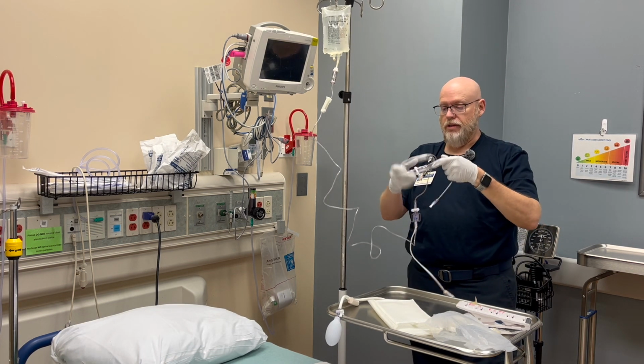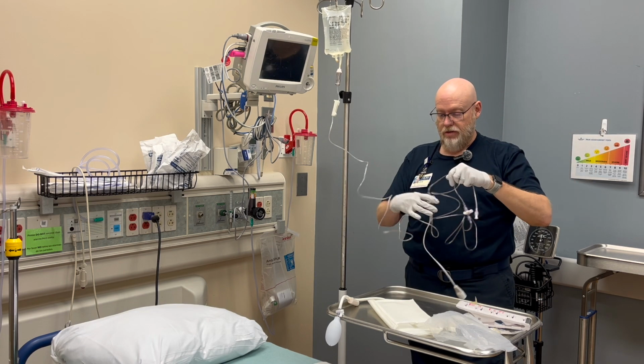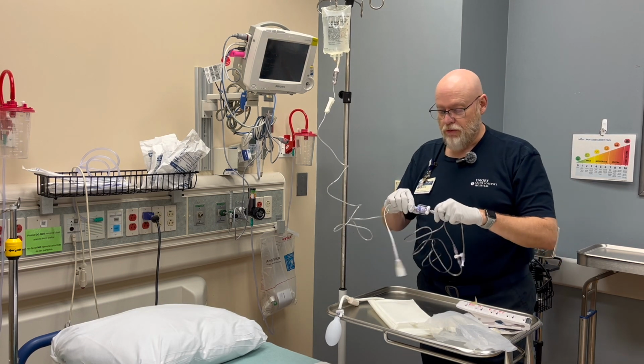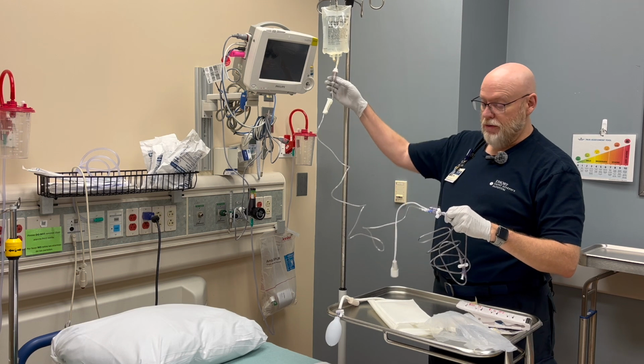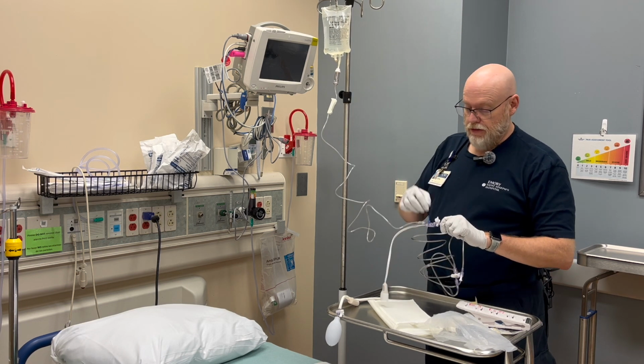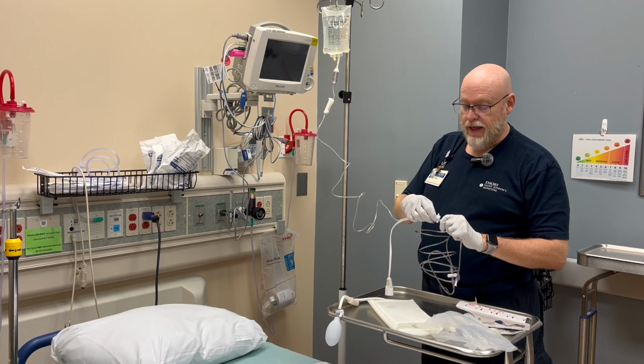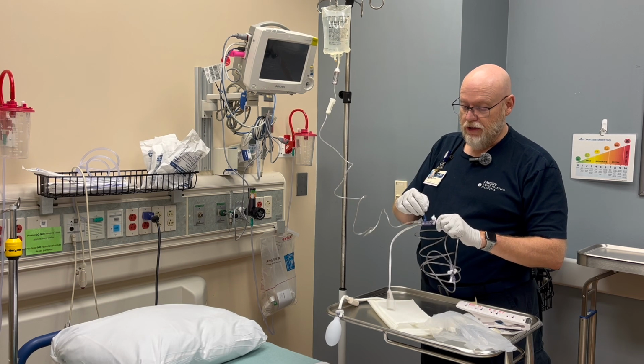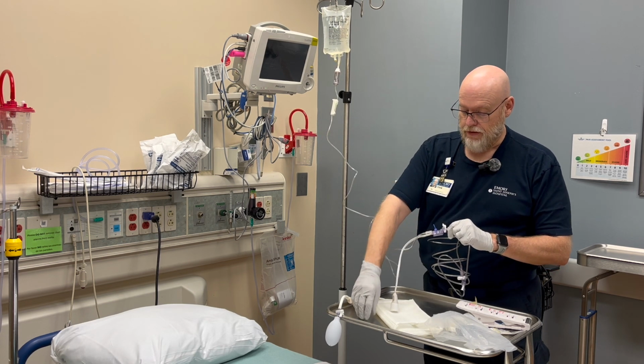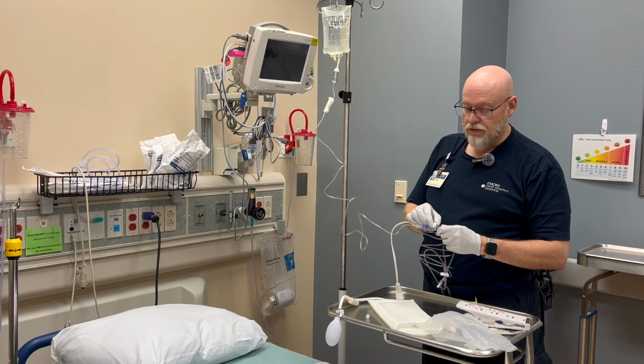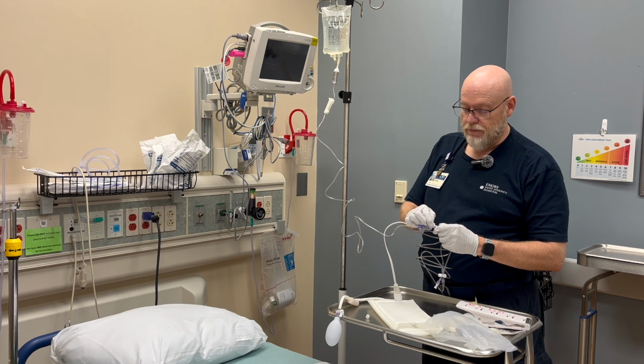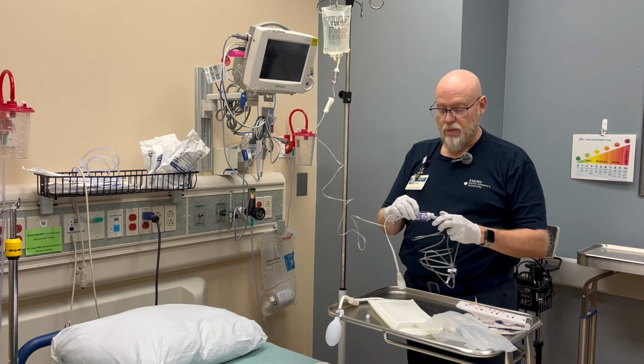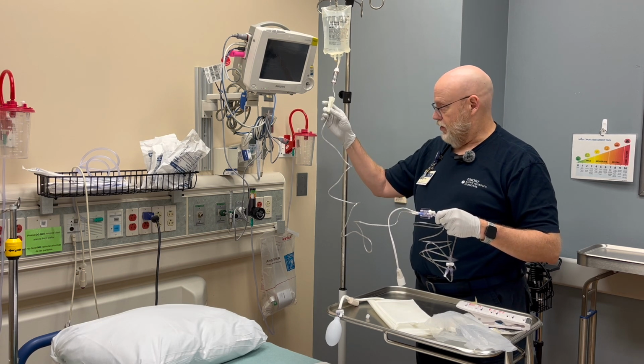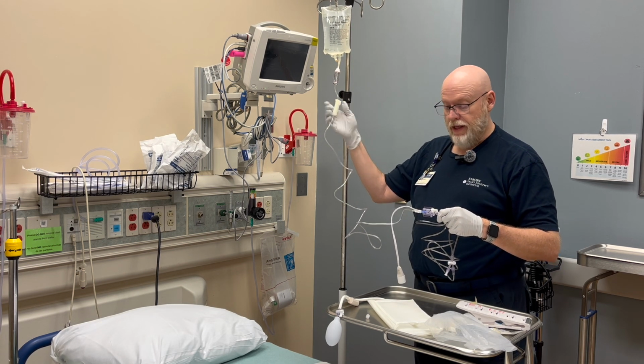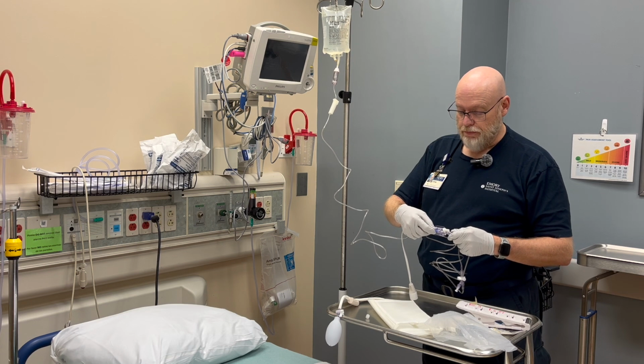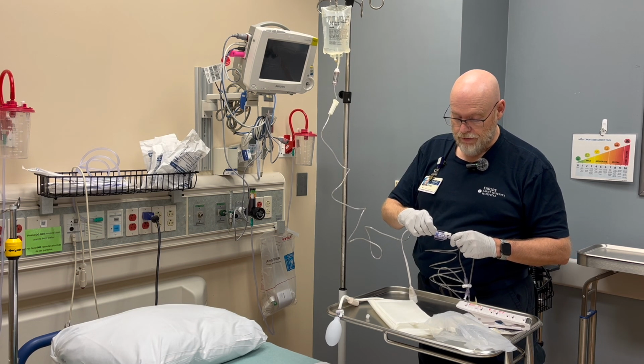Okay, the next part is important that you do this correctly. You're going to want to prime the tubing from the drip chamber down to the transducer. There is a white cap that's on the clear cap that is on the stopcock. You can take that off, leave it open. You're then going to turn the stopcock off to the patient side, which if you're holding it this way, it's going to be to your left. Then you're going to unclamp the roller clamp. You're going to take and pull the blue pigtail until it comes out to this port.